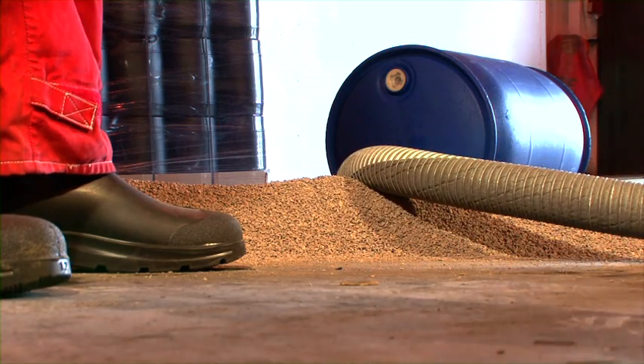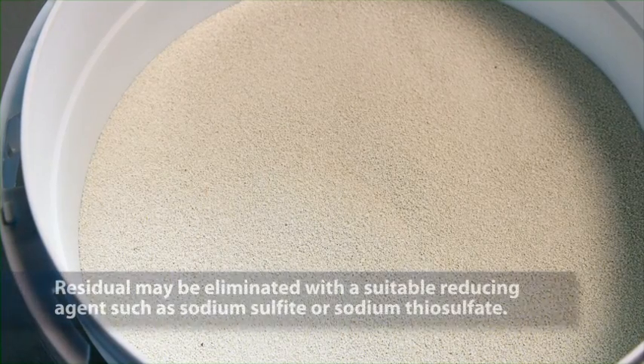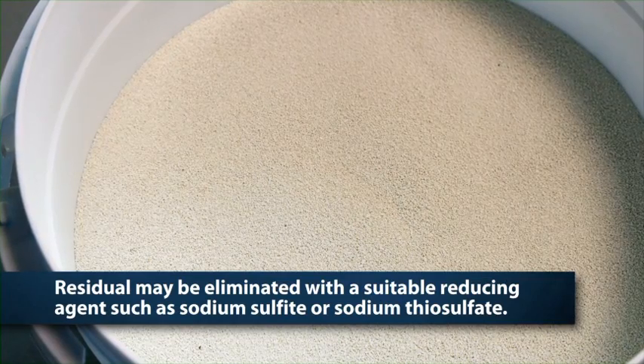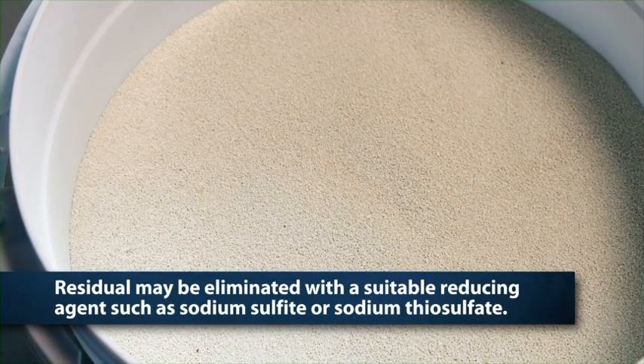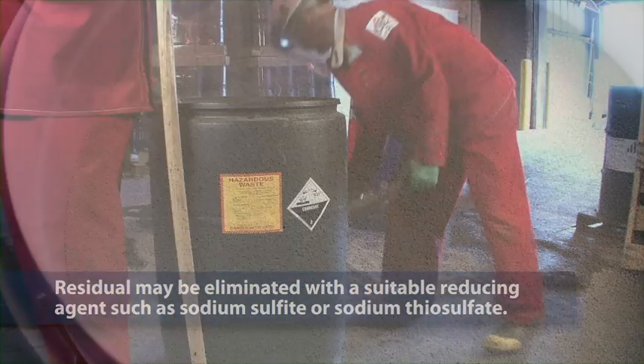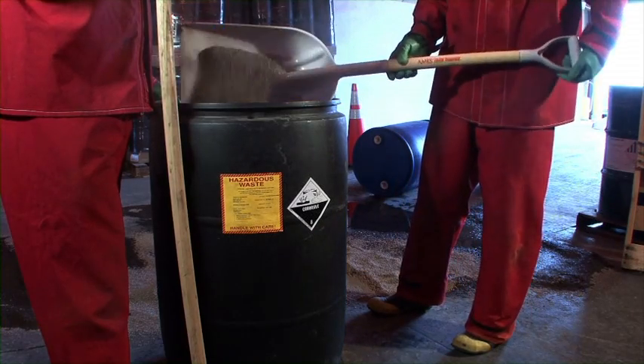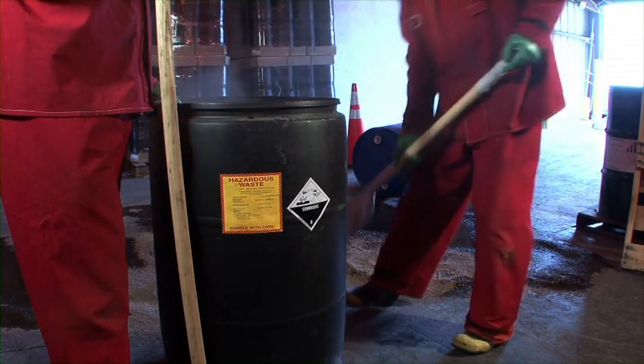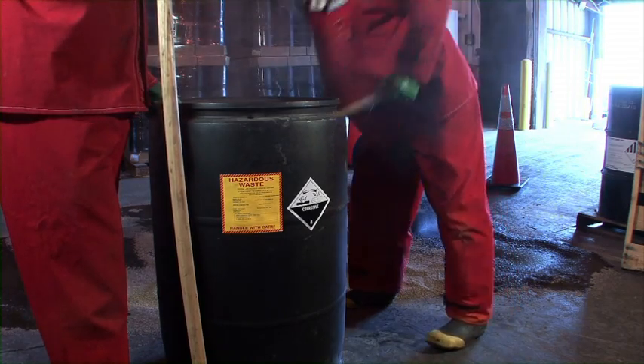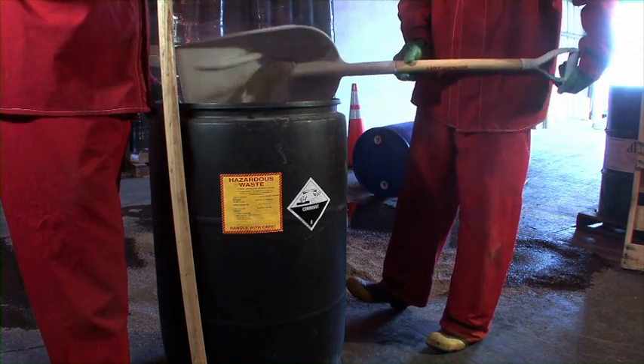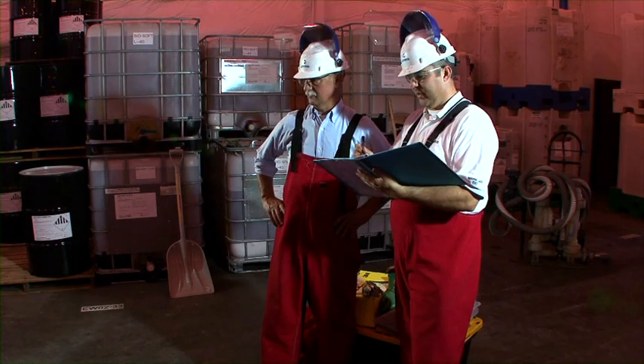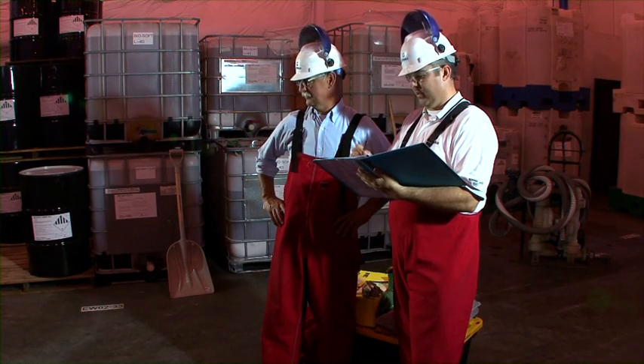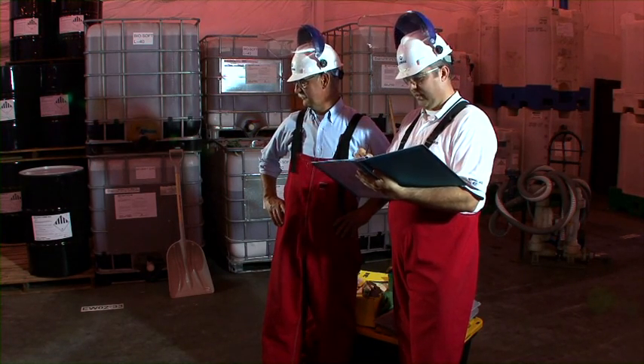Any residual that remains from the spill may be eliminated with a suitable reducing agent, such as sodium sulfite or sodium thiosulfate. Recover the waste and dispose of it and any absorbent material by following all state and federal guidelines and regulations. You may be required to report the spill according to applicable federal, state, provincial, and/or local regulations.